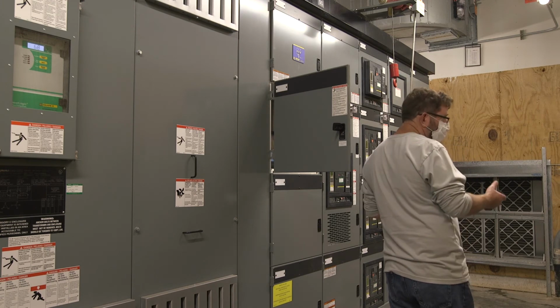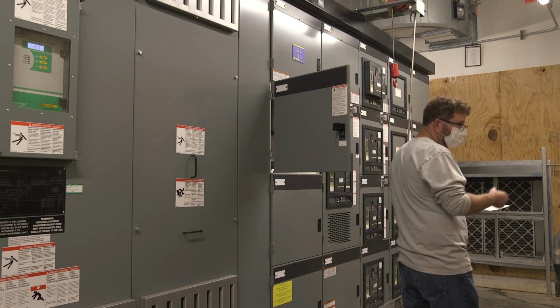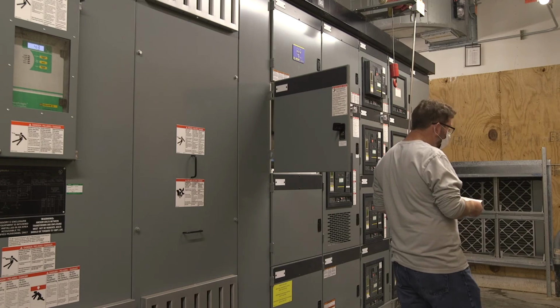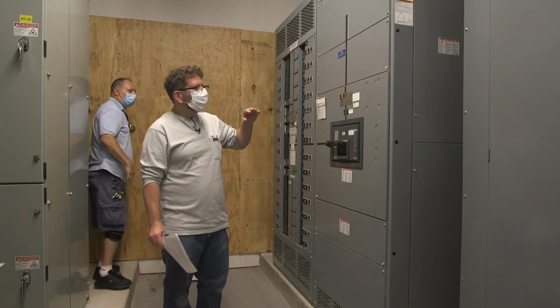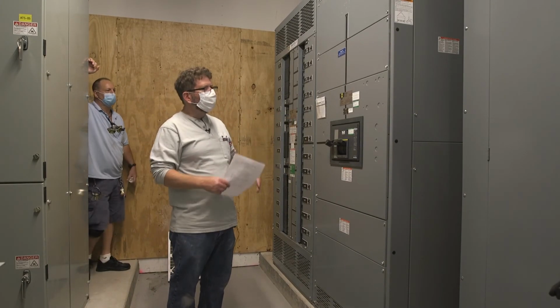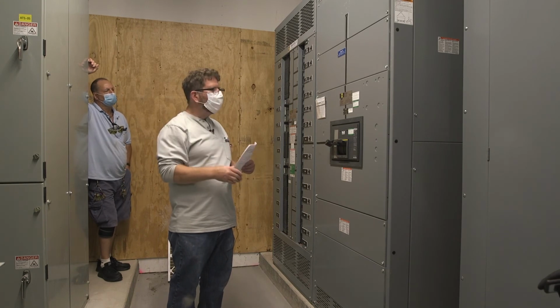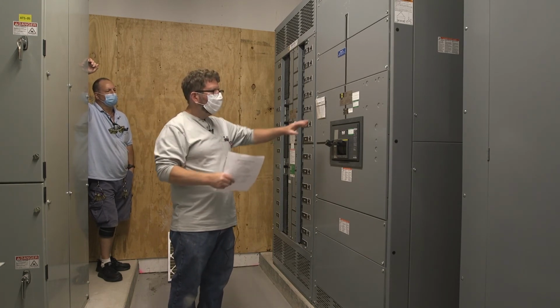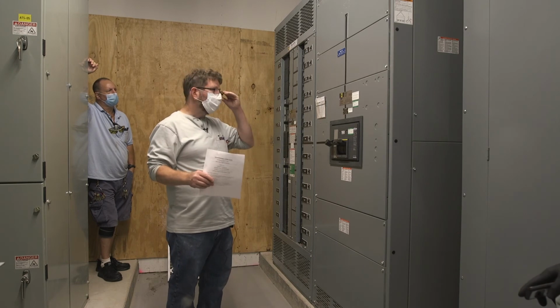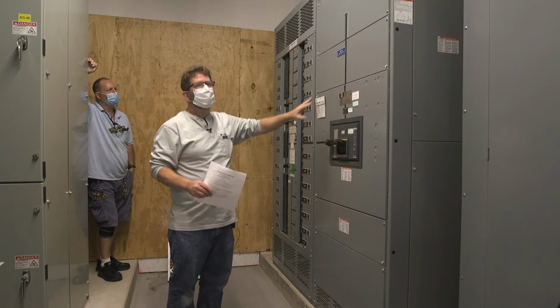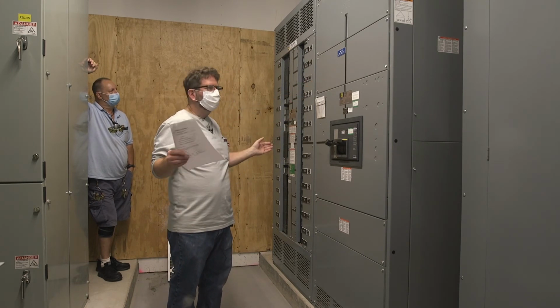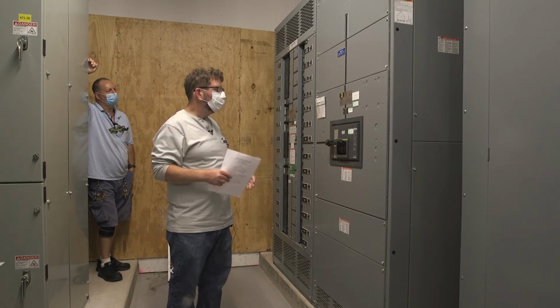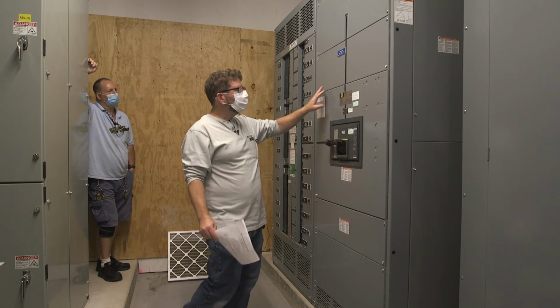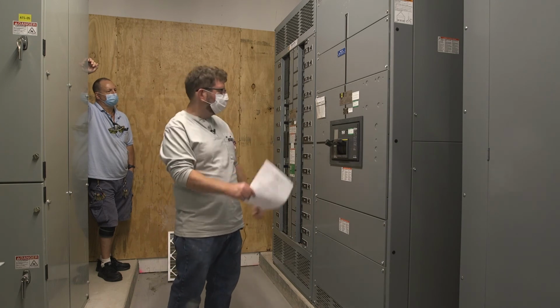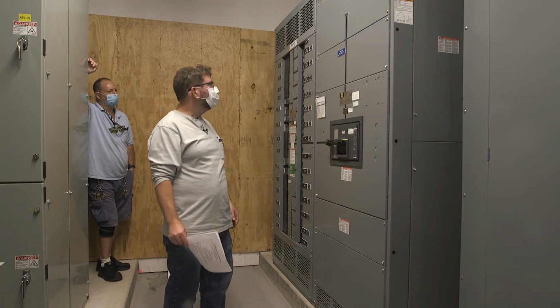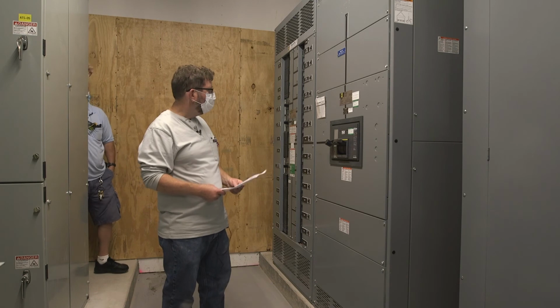Okay, we have another electric room, I guess right next to here. This is our QED style switchboard. The last one was Power Zone 4. It's compartmentalized. QED is not compartmentalized. If you open up this cover, you're going to have 480 volt bus exposed. So it's really not built for opening up unless you de-energize it.